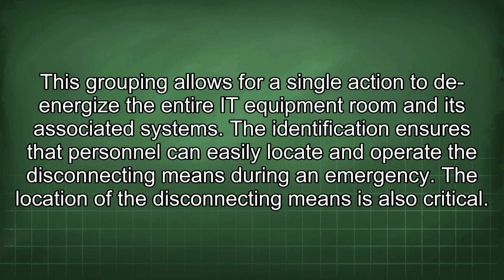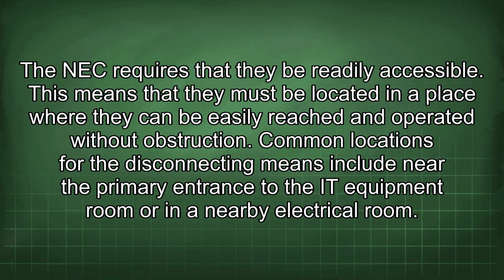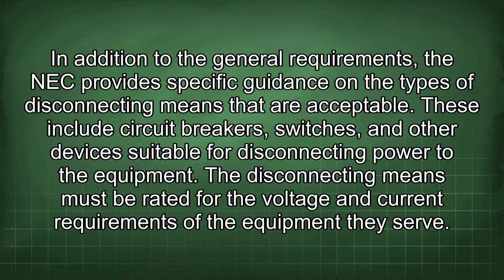The location of the disconnecting means is also critical. The NEC requires that they be readily accessible. This means that they must be located in a place where they can be easily reached and operated without obstruction. Common locations for the disconnecting means include near the primary entrance to the IT equipment room or in a nearby electrical room.